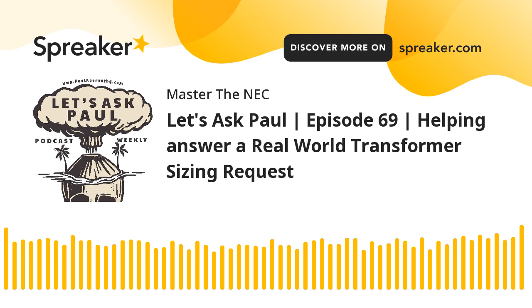So if I don't exceed 125% on the primary, then I don't require any secondary protection for this transformer. So that's typically why we follow that. All right, so let's kind of do this and work our way out. I'm just giving you my thoughts here on how I would do this for your question. All right, so you got your code book. Go to 450.3(B), and we're going to do primary only protection.